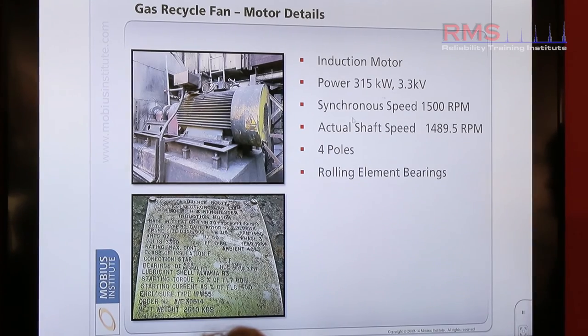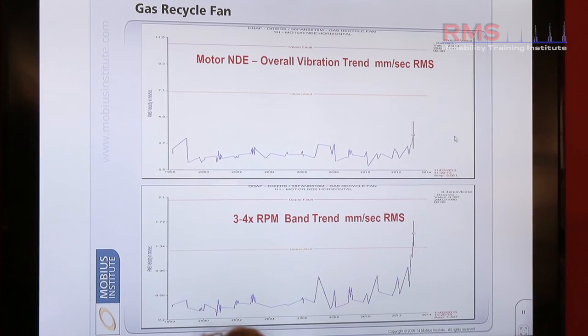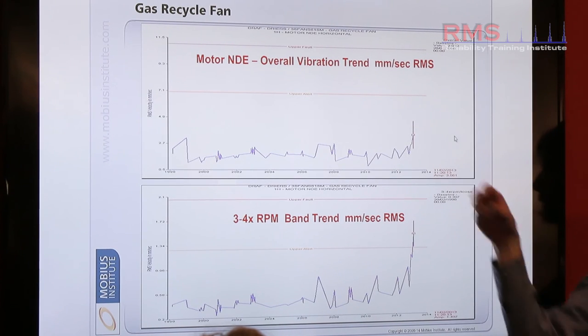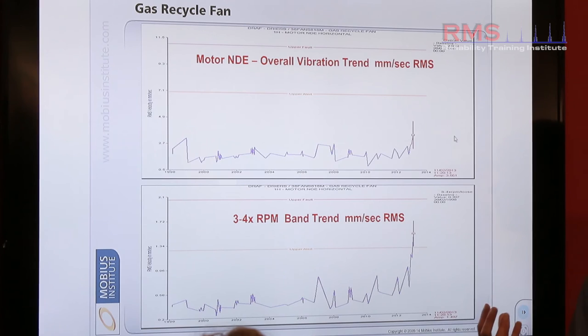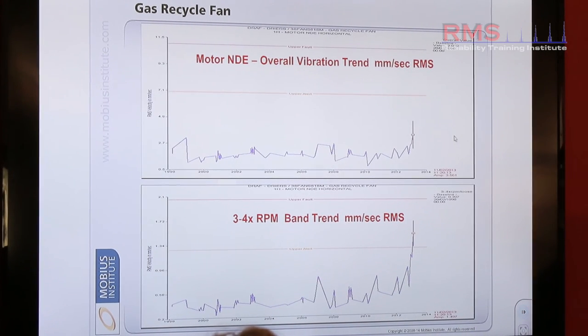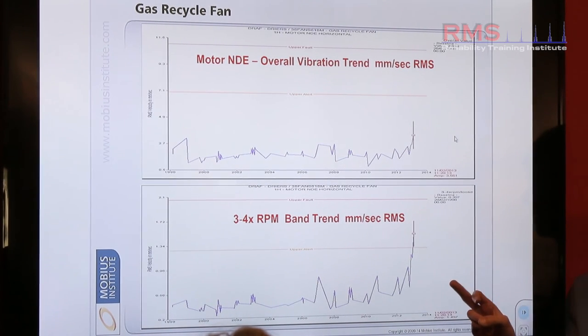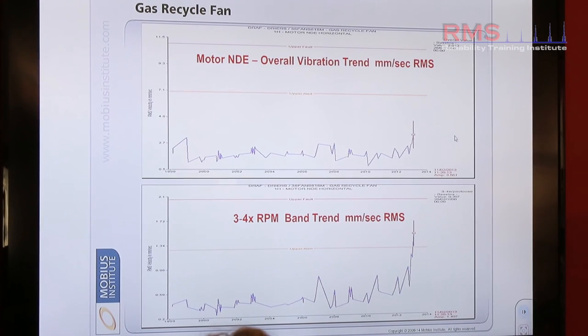A bit of detail about the machine: 315 kilowatts, 1500 RPM less slip. So my general vibration trend, according to an ISO standard, was actually well within tolerance. But because it's important not just to trend the general level of vibration — perhaps different parts of the vibration, the different heartbeats — you can trend them independently. This particular trend segment here violated an alarm.